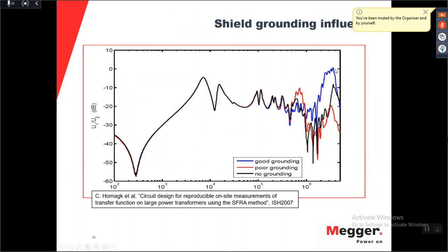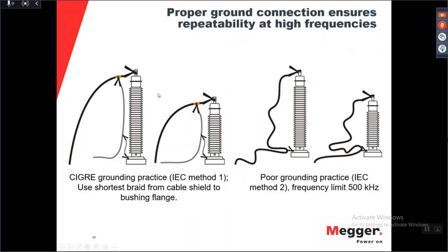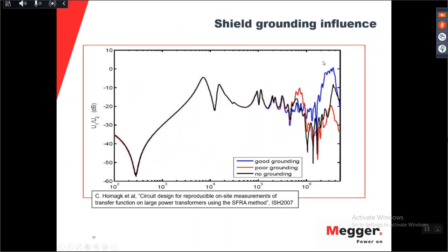And you should be able to repeat the blue line. If you have the poor grounding, you can see how the higher frequency actually differentiates above 500 kilohertz. If you have no grounding, you have something here in between. So it is very difficult to repeat the same measurement circuit unless you have the proper shield ground practice. That's why they recommend method 1. And as you can see, this small difference in connection gives this difference in high frequency response.